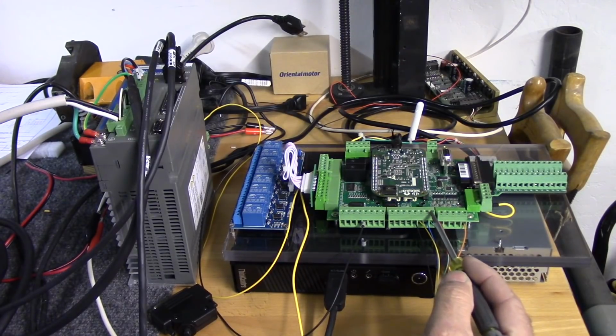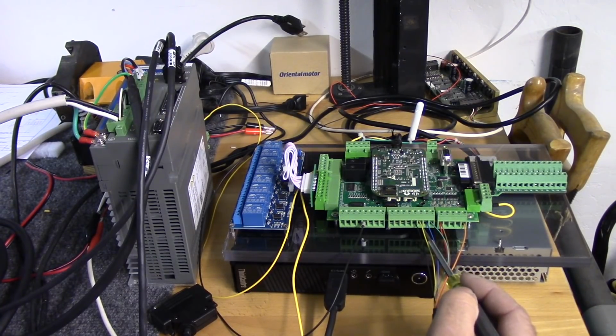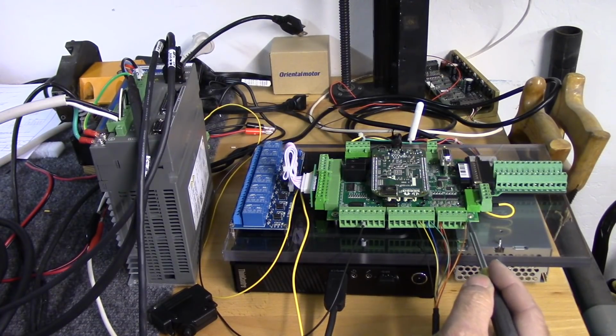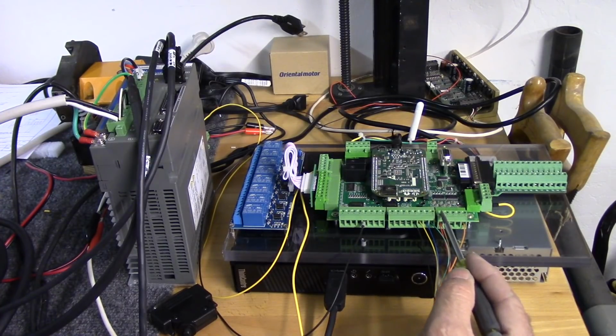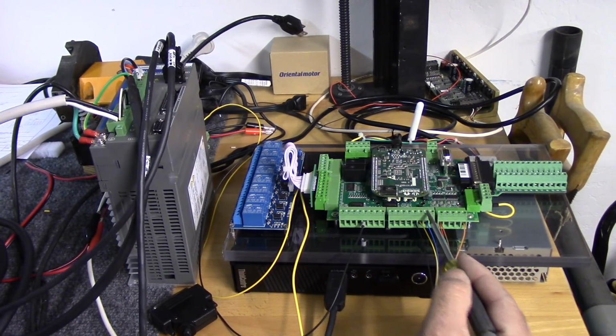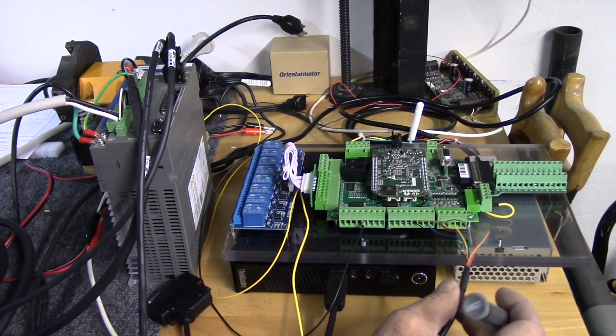So the next one over, this is axis 1, this is step. Step is the green wire. So ST1 is green wire. Direction is the blue wire. Enable is the yellow wire. And common is the black wire. So to recap, the orange is on input 5, the brown and the red are on 24 volt supply, the green is on step, the blue is on direction, the yellow is on enable, and the black is on common. That's it. That's all there is to it.